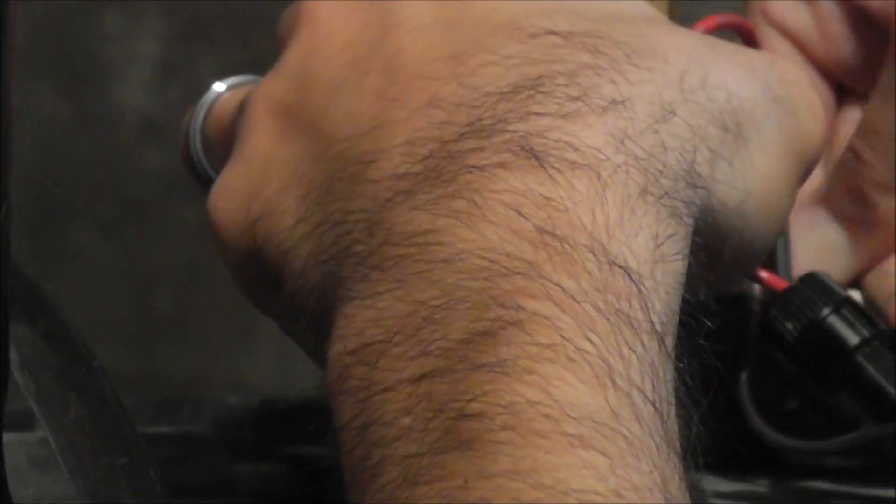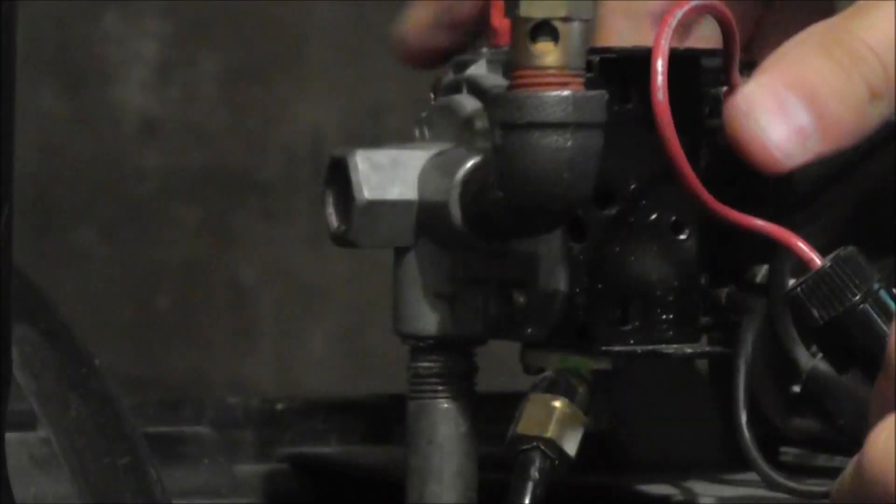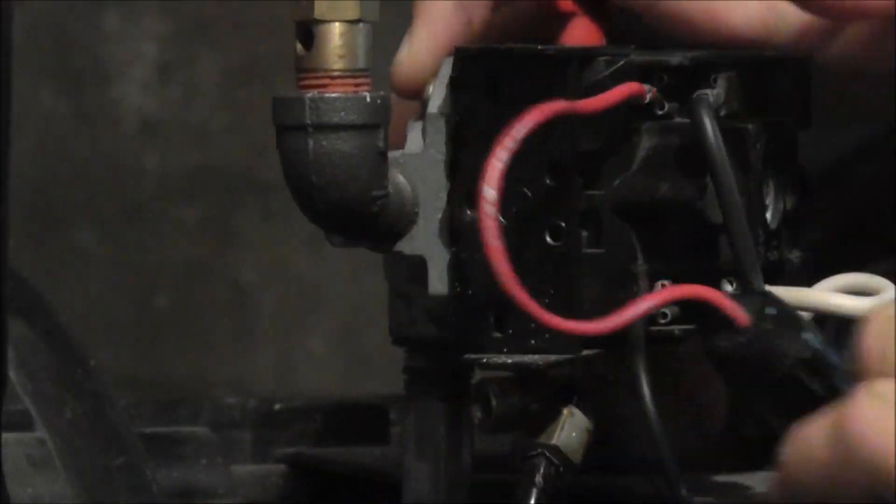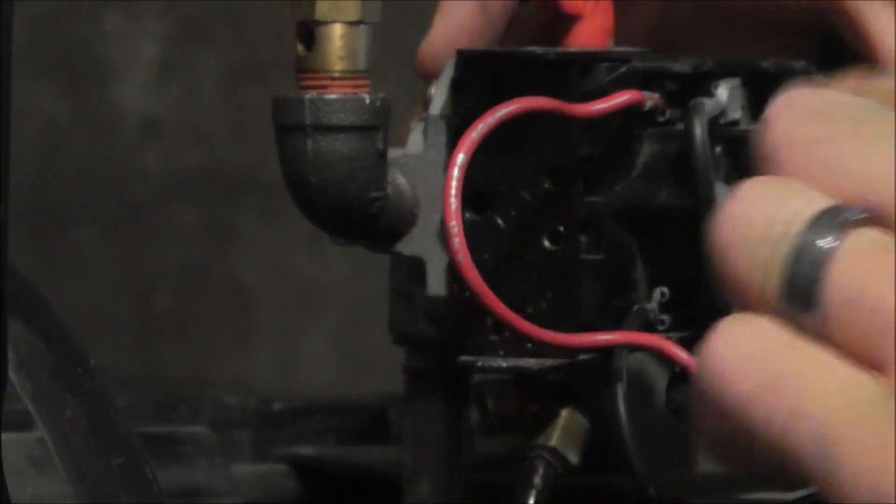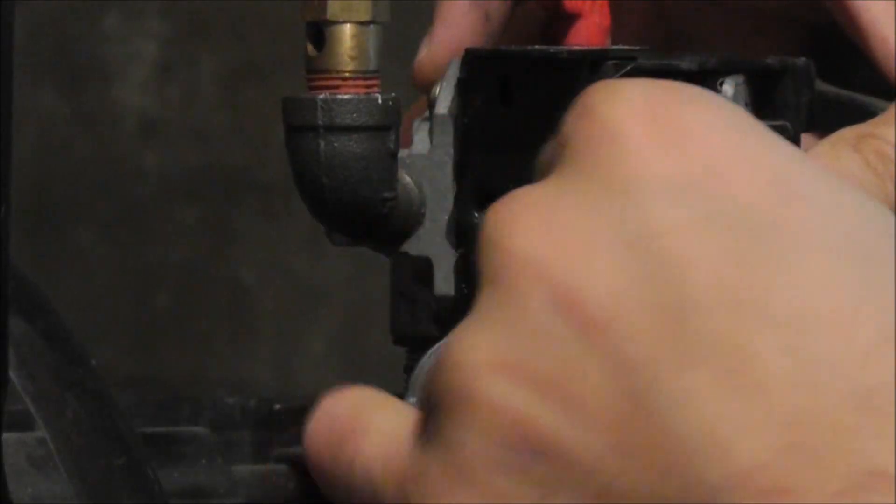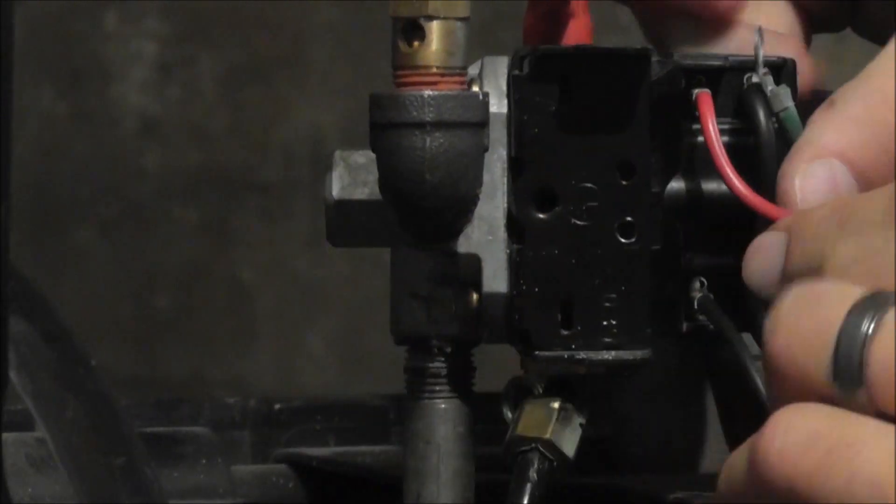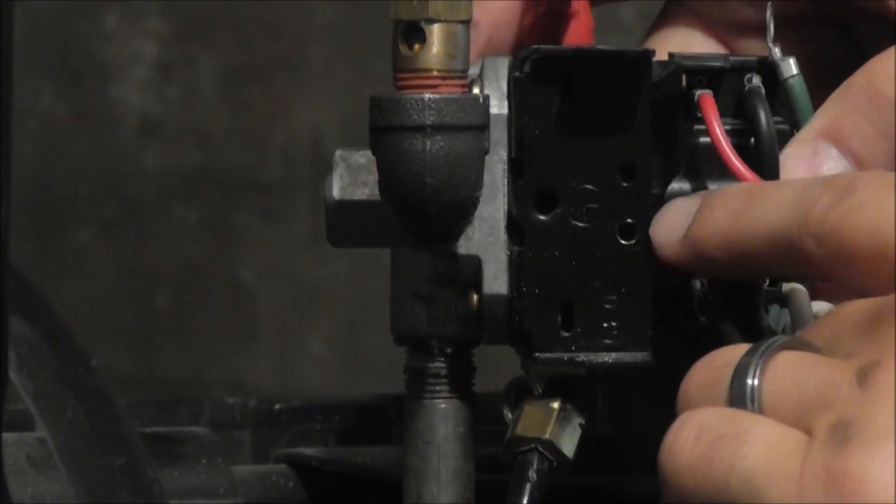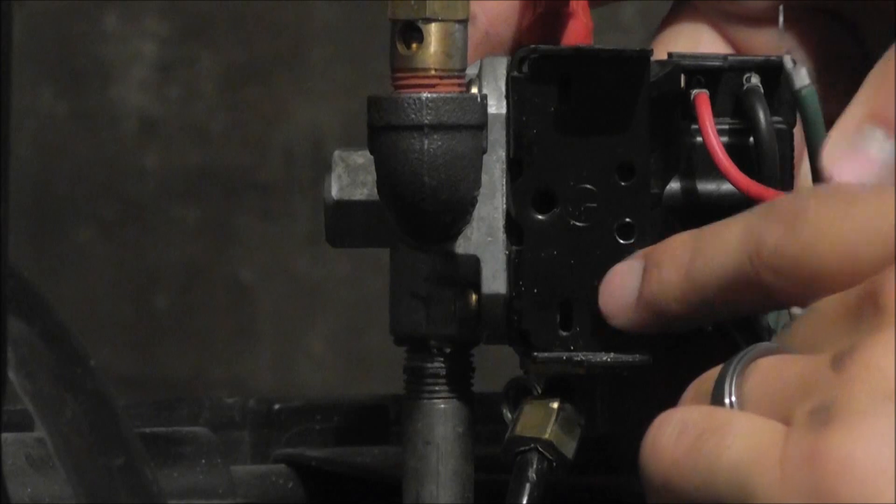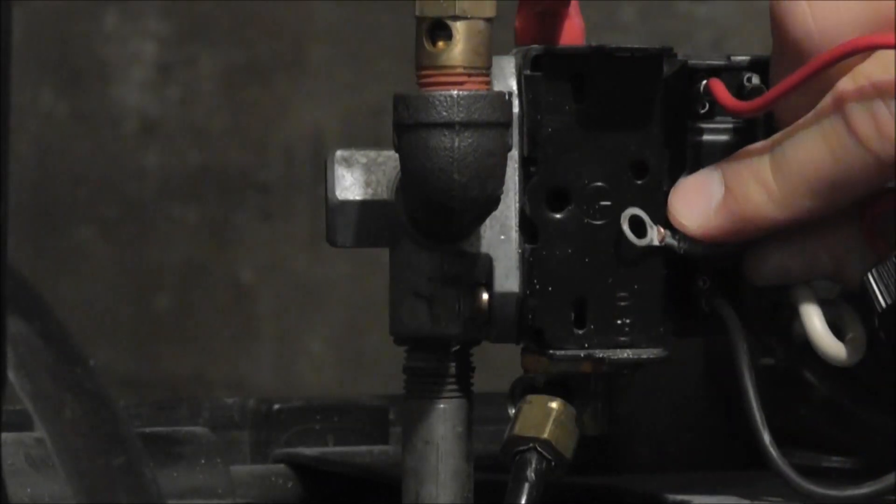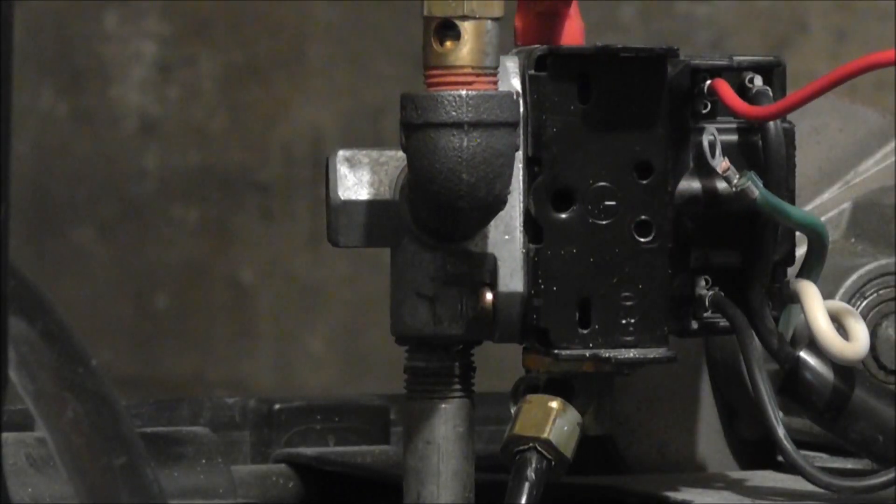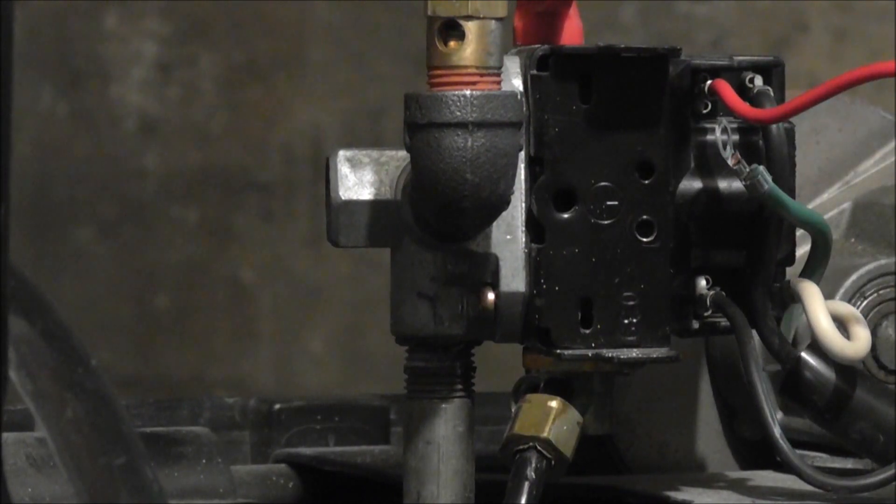And you're going to have your motor ground wire as well. So here we have the wired pressure switch, black and white from the power cord, and red and black from the motor. And your ground screw will be attached on the base, the metal base of this switch. It'll be attached here with a screw, your ground screw. This is green. And that will ground the unit.